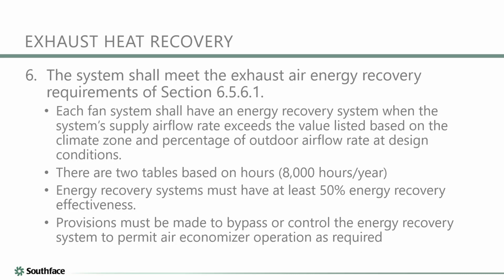All right, the next requirement here is for exhaust heat recovery. So basically, if you have an exhaust system, you need to be able to recover some of that energy or some of that heat before you dump all that air out of the building. There are a couple of requirements here, and basically the system must exceed the value listed based on those climate zones. So again, that's going to be a table lookup in the code book. And then there are two tables based on the number of hours that the equipment is going to be running. Basically the threshold is 8,000. If you're less than 8,000, you look up one table, and if you're more than 8,000, it's another. And they must be able to recover at least 50% of the energy.